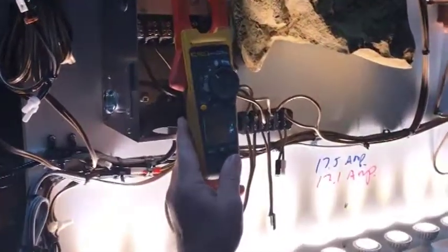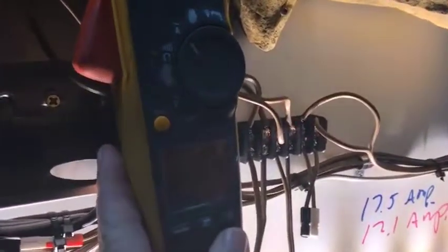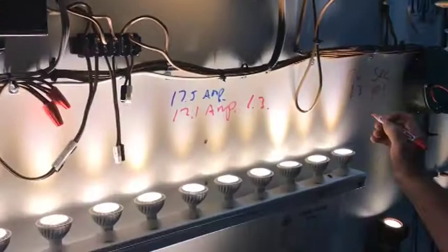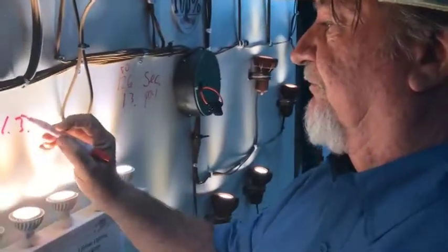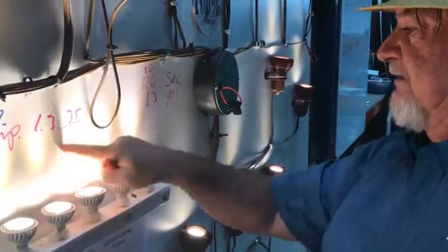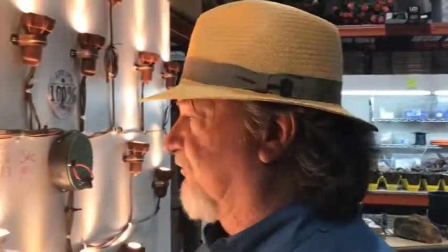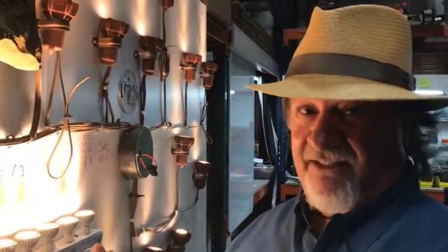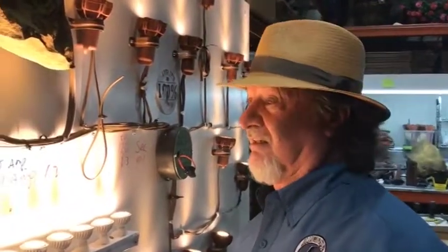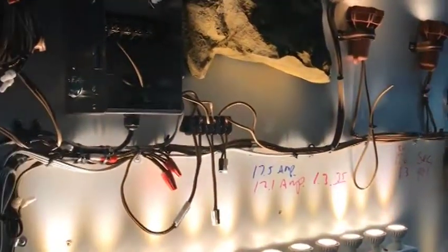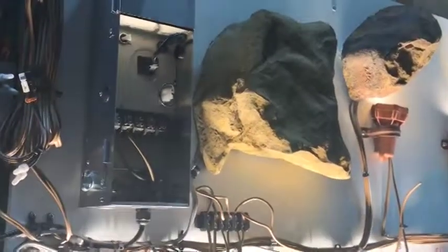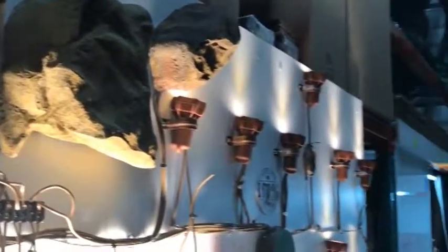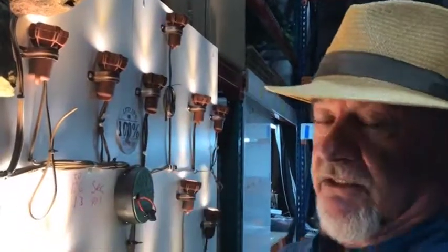Check the primary. 1.3. So you can see that we had 50 lamps over here, and we have 35 over here. We're pulling the same amount of amperage, right? That's how efficient these high efficiency, low voltage transformers are. That's 15 lamps for free with the same electricity, all right? The other advantages, now we're going to go over quite a few. There's really 16 different advantages to go with a power supply versus a dumb transformer.